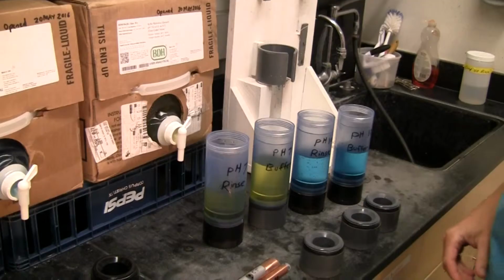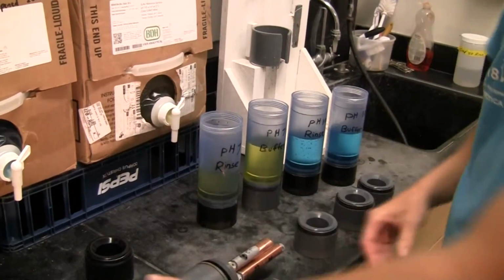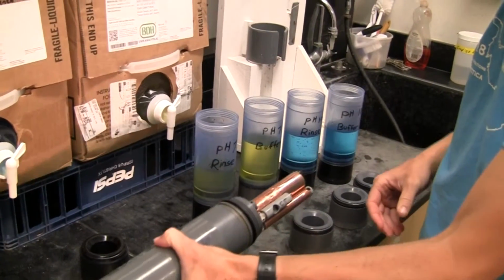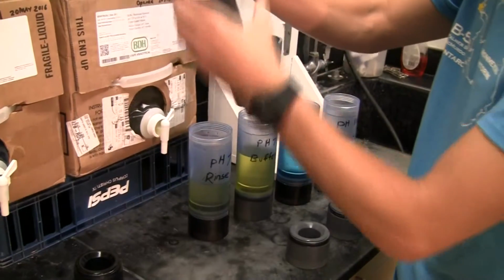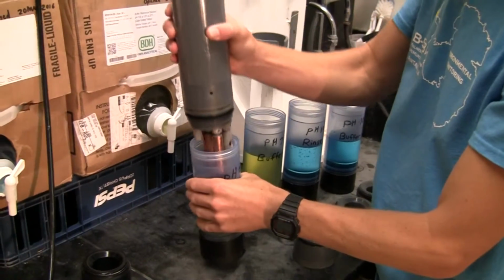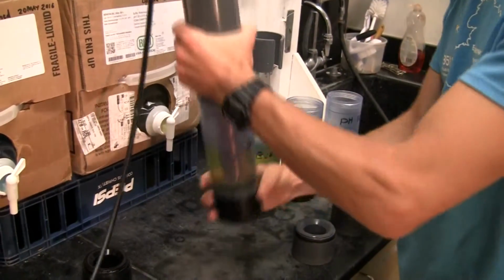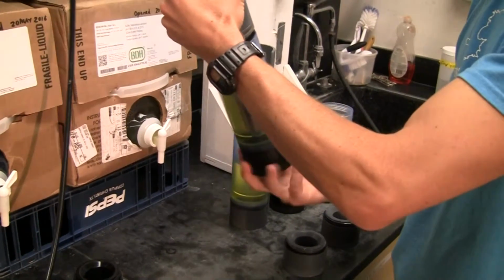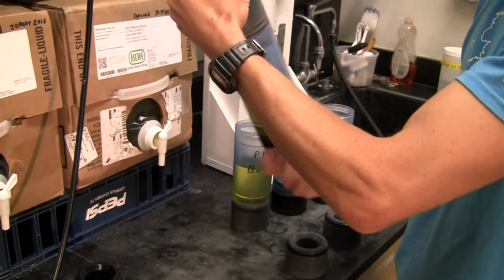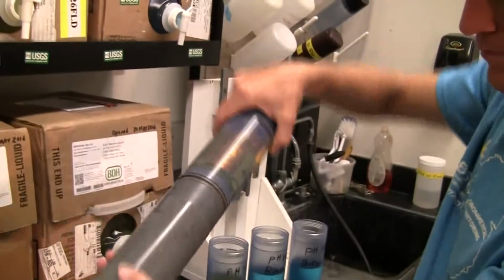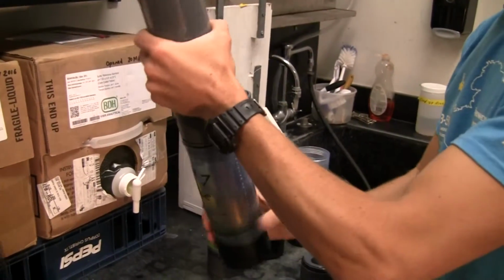Now that we have the containers ready, we're going to go ahead and start the calibration procedure. So we place the sensor head unit in the pH 7 rinse. Flip it upside down to make sure that the sensor is completely rinsed with the standard.